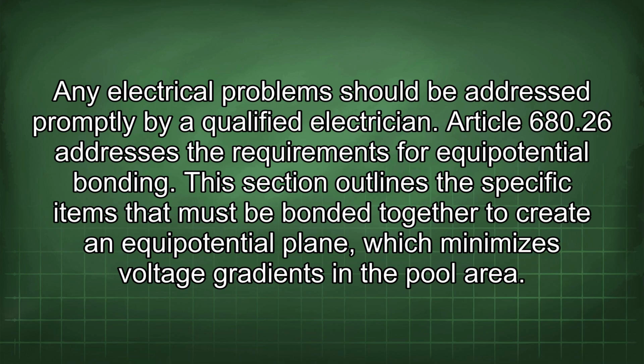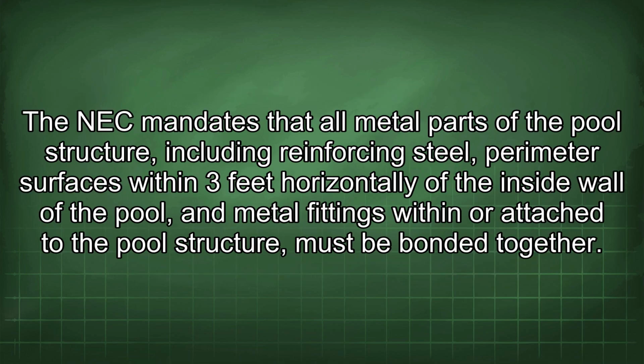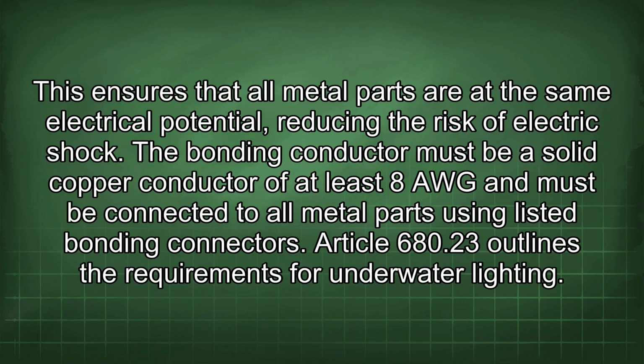Article 680.26 addresses the requirements for equipotential bonding. This section outlines the specific items that must be bonded together to create an equipotential plane, which minimizes voltage gradients in the pool area. The NEC mandates that all metal parts of the pool structure, including reinforcing steel, perimeter surfaces within 3 feet horizontally of the inside wall of the pool, and metal fittings within or attached to the pool structure, must be bonded together. This ensures that all metal parts are at the same electrical potential, reducing the risk of electric shock. The bonding conductor must be a solid copper conductor of at least 8 AWG and must be connected to all metal parts using listed bonding connectors.